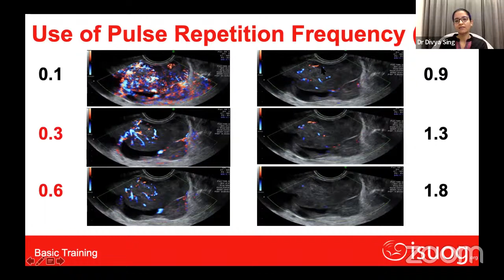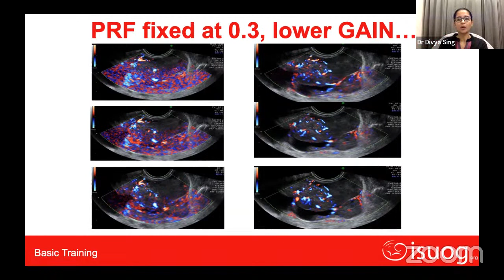Once you've fixed the PRF, say at 0.3 kilohertz, then you adjust the gain. You can always initially increase the gain so that the gain is more than what is required, as you see in this first image. The color is kind of filling up the whole box. And after that, you start reducing the gain by adjusting the knob such that the color doesn't occupy the entire box in this fashion and is confined to the solid area of interest, as you see in these images. So you can work from excess gain, reduce it slowly till you get the optimal gain.